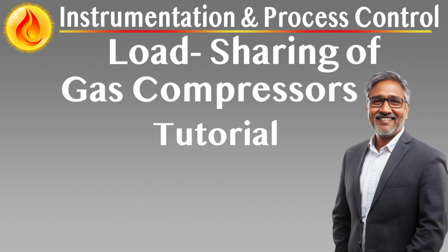Activation conditions and control scenarios. Pressure override control is triggered under the following conditions. Discharge pressure control mode: override is initiated if the pressure rises too high or too quickly. Suction pressure control mode: override is activated when pressure falls too low or too rapidly. In either mode, the objective is the same: prevent excursions that might cause overloading, trip events, or damage to downstream equipment, while still maintaining surge protection integrity.